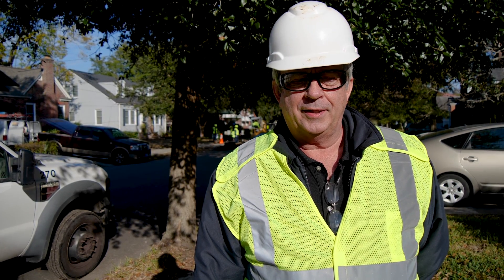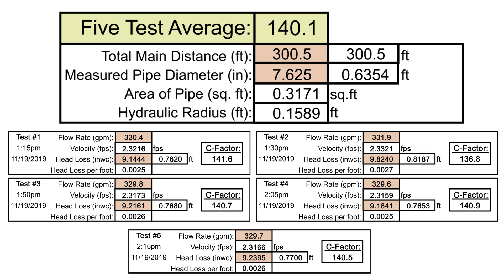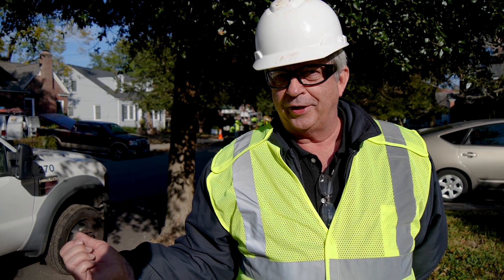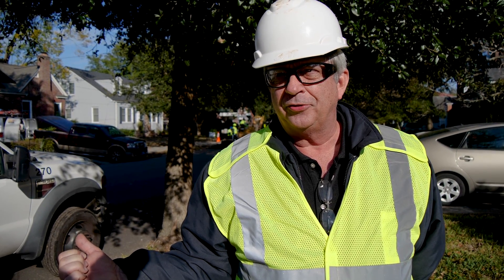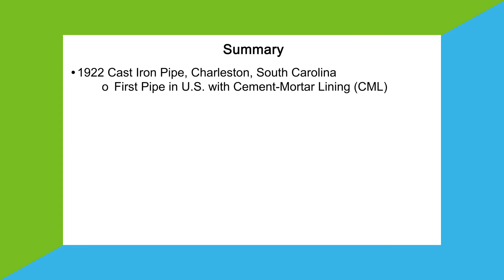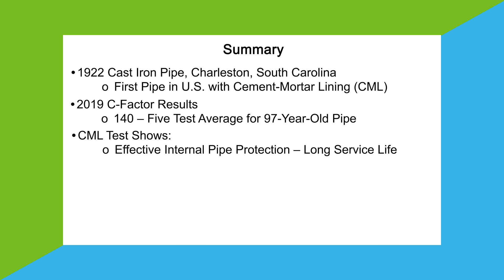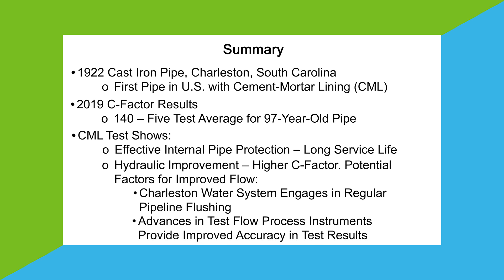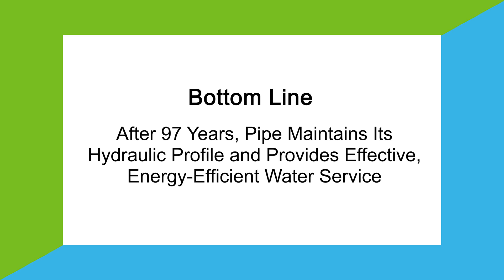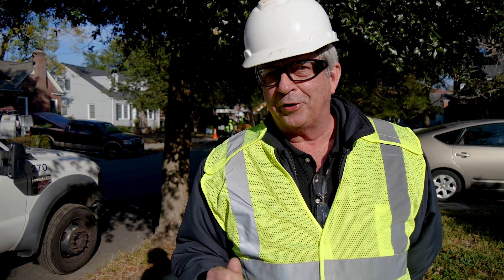We've completed our test today. We use these tests to evaluate the C factors that we get in the field in actual pipelines. The recommendation that our industry makes is that the C factor of 140 is the average of all of the in-situ tests we've done over the years. The results we got here today were excellent. This is a 97-year-old pipeline — the first ever to be provided with a cement mortar lining in the United States. The results indicate that the cement mortar lining is doing its job: protecting the pipe from internal corrosion, providing a better hydraulic profile, which saves energy when pumping water. After 97 years, it's showing that the hydraulic profile is maintaining its good characteristics, protecting the pipe and keeping the water flowing very smoothly.